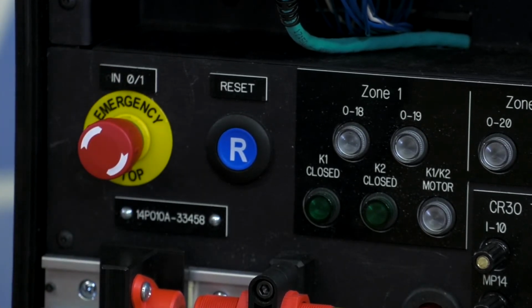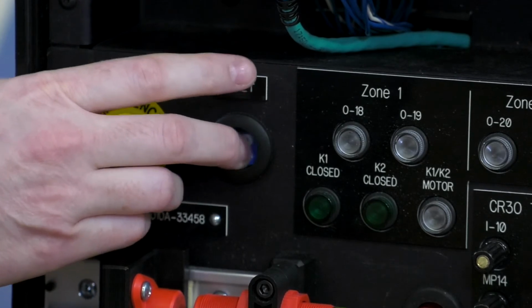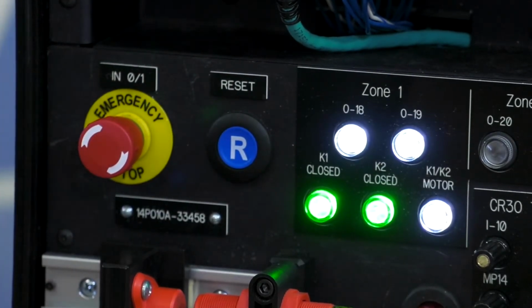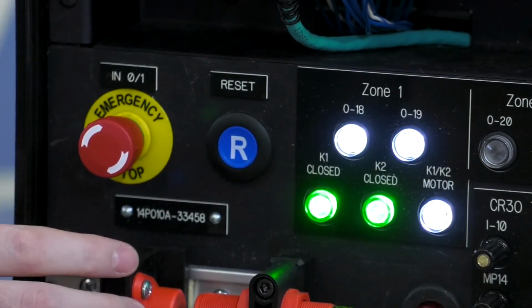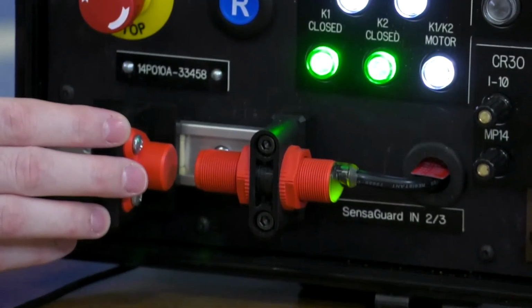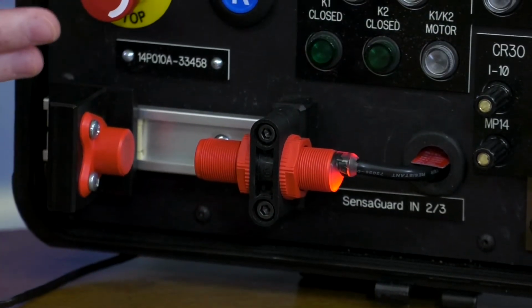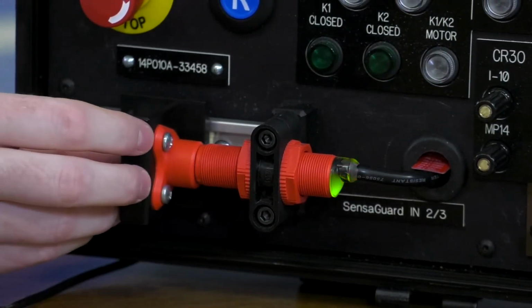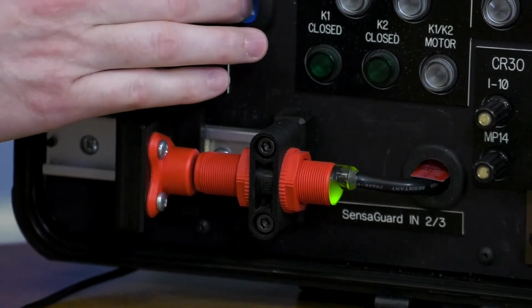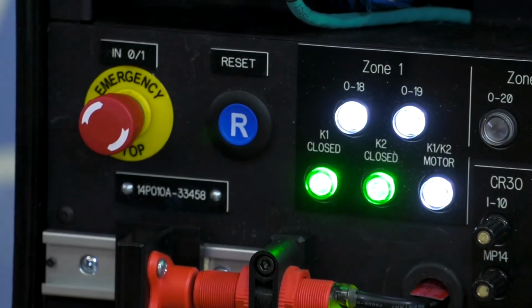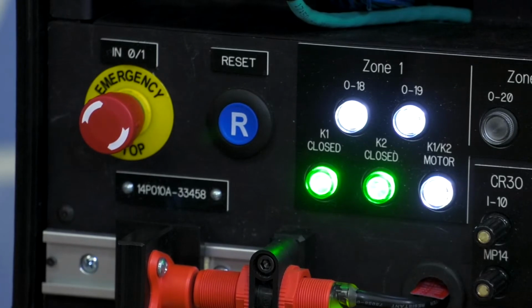Turn the e-stop back on. Notice how it doesn't turn on right away. It requires a reset. So we're going to click on reset. That part's good. Now we'll test our gate switch. So I'll open this gate switch. Everything turns off. We're all good. Close the gate switch. Hit our reset, everything's perfect.